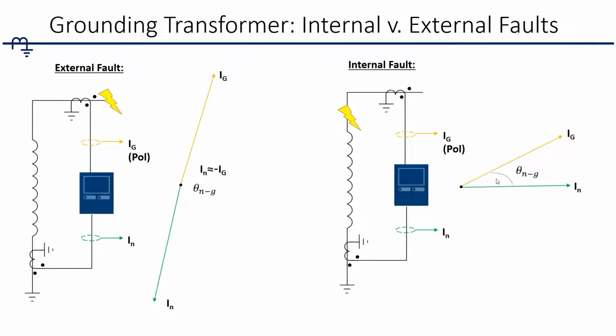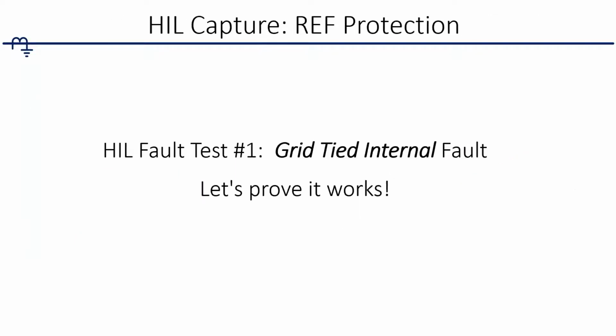For internal faults, you're going to see a pretty narrow angle here, is what you typically see. And I'll give you guys some examples of actual data we collected with the HIL showing this. So this is kind of what to expect, so keep that in mind as we go through this. You see a wide angle at 180 degrees, that's an external fault. You start seeing these narrow angles like this, it's an internal fault in the transformer. So that's what the relay is using as an operate quantity.